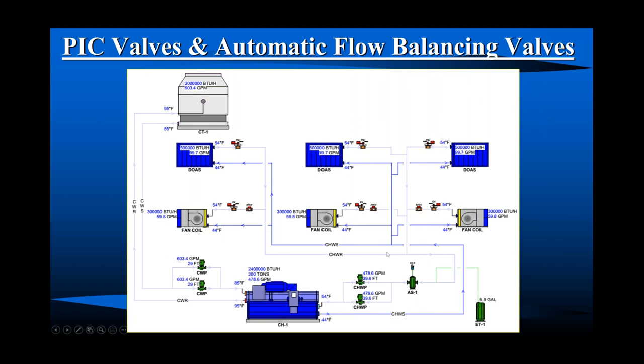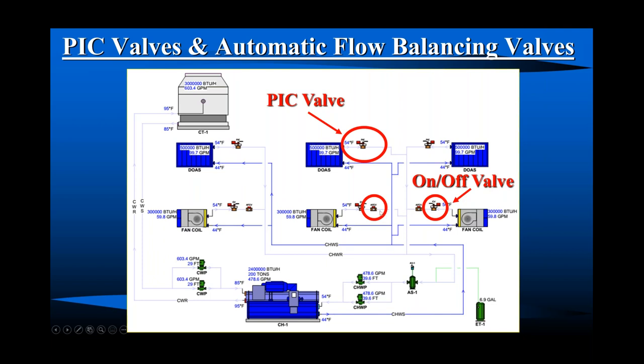So if we did have a pump set that's serving both a PIC valve system, right? If we did use a hydronic coil for our DOAS unit, we'd probably use a PIC valve on that coil. For our fan coils, which are on-off, flow present or not present, we'd probably use a two-way control valve, which is fine. But that balancing valve on that fan coil really should be an automatic flow balancing valve. Because if this pump set is serving both, this is a flow limiter and this should be as well.